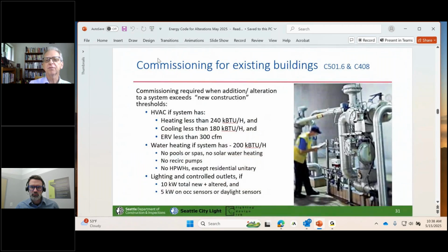Commissioning is another thing for existing buildings we have to watch out for, and it follows the same kind of new construction rules. You see those different thresholds for how big your system has to be before it needs commissioning. So if you're doing an addition or alteration that replaces or changes out more than those threshold amounts, you'd need to do commissioning. And if you only have 1 or 2 of those 3 things, you'd just do the commissioning for those 1 or 2.